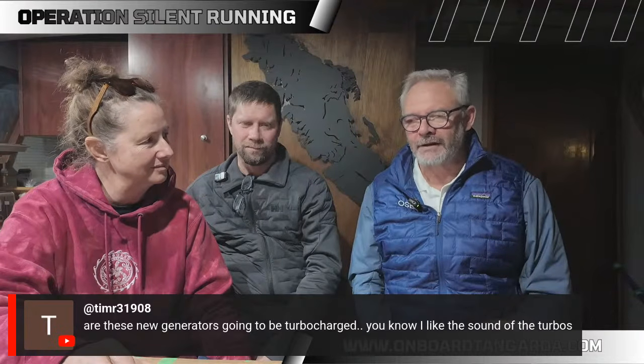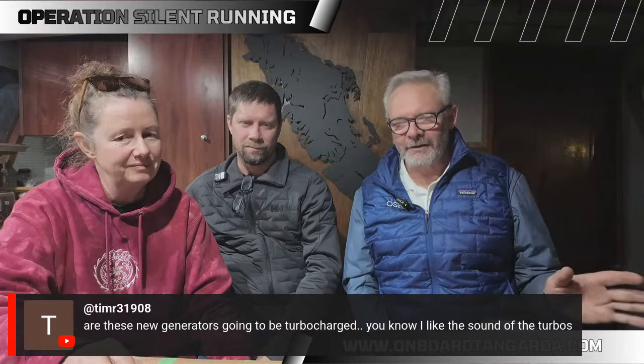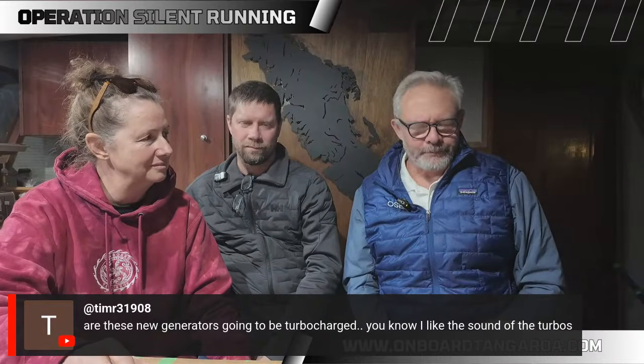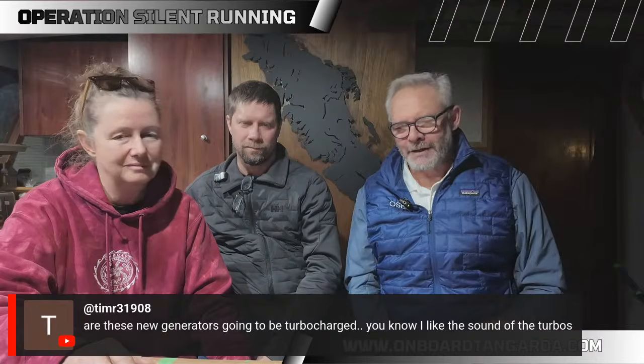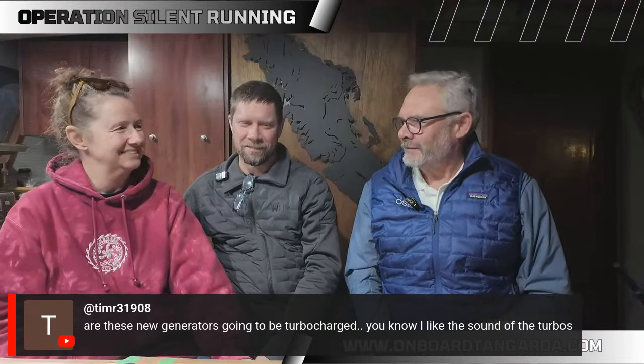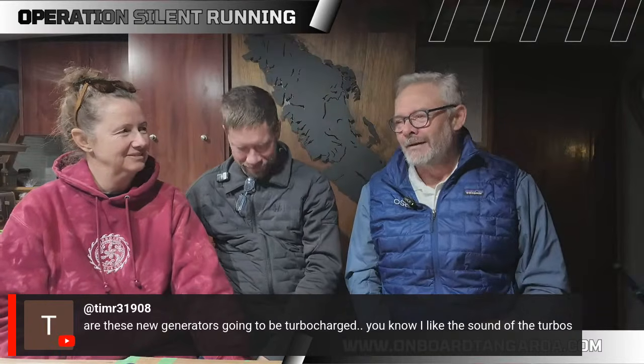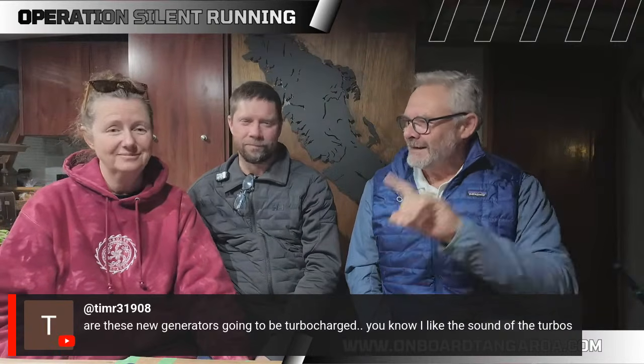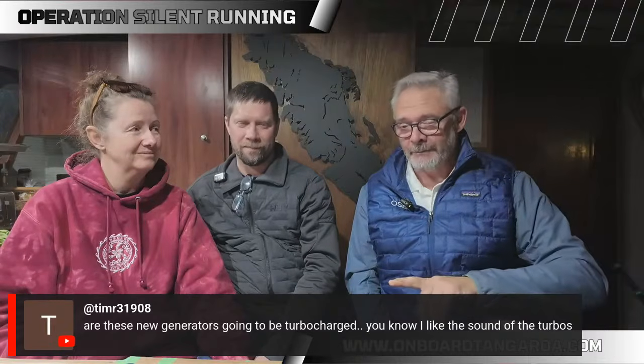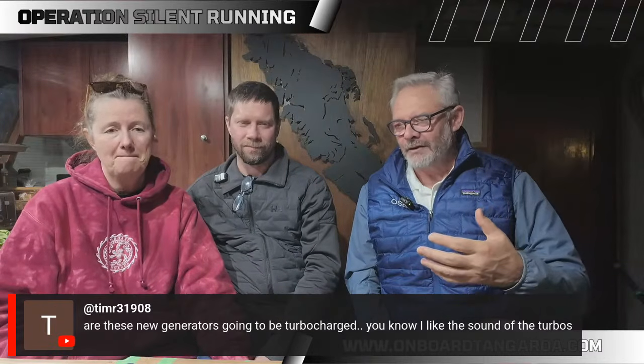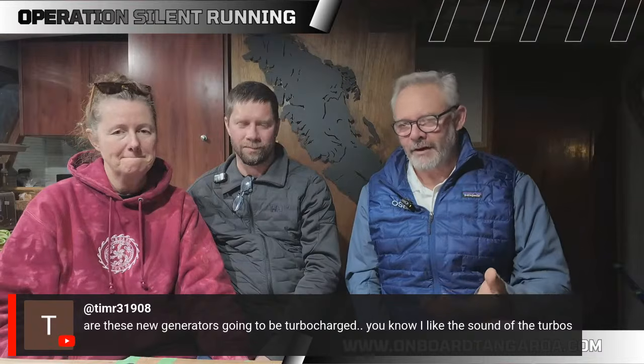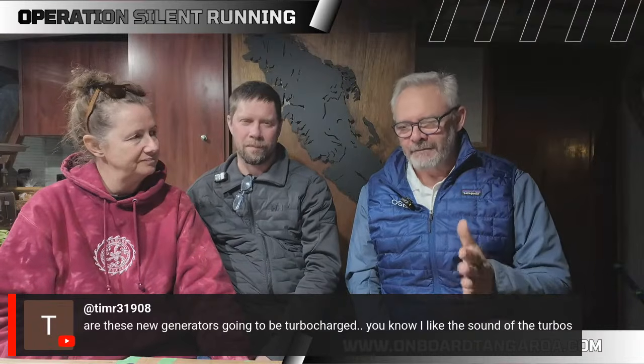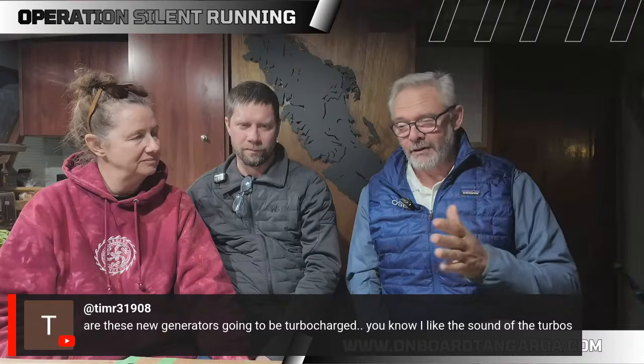It quickly settled in that the generator would stall out at about 18 and a half. That may have nothing to do with the generator, it could be my installation, the exhaust system, a number of things. But their answer was, well, it shouldn't be running that hard all the time, you should run it at 70% and 50% for some period of the time. And I said, well, that's great information yesterday, it's not great information today. So it taught me we had to go back and clarify with our suppliers on this case, 50 kilowatt hour or 50 kilowatts continuous.